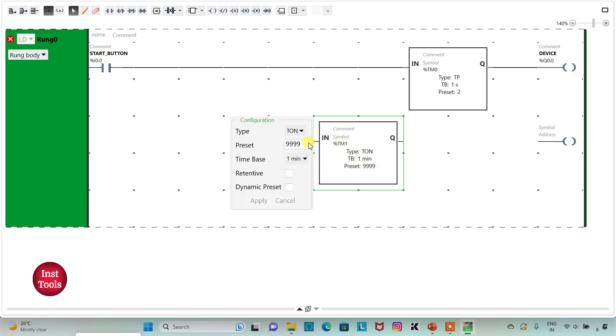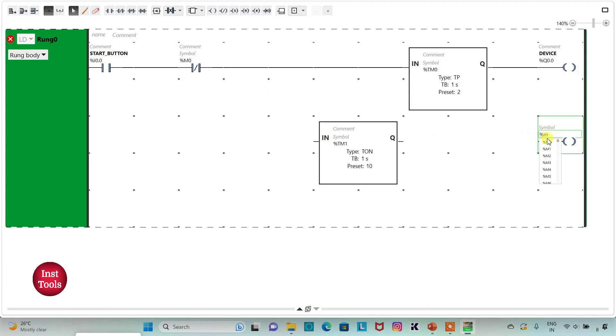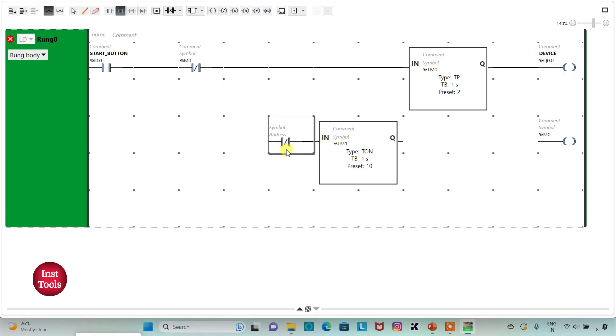The second timer should be T-ON with a preset value of 10 seconds, time base as seconds — then click Apply. I will insert a normally closed contact and assign address M0 (a memory bit) to it. I will assign the same address M0 to the coil. Then I will add another normally closed contact with address Q 0.0 (the device) and draw a connecting line.